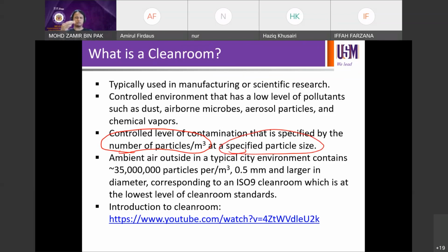So to put things into perspective, ambient air outside, if you go out to, say, Sungai Dua or Bayan Lepas, depending on the area of course, in a typical city environment like Georgetown, typically contains about 35 million particles per cubic meter. Yeah, 35 million particles per cubic meter. 1 meter by 1 meter by 1 meter. One box. With size 0.5 micron and larger in diameter. If you go to Georgetown, perhaps this is the typical number of particles that you will find in 1 cubic meter. 35 million particles, with sizes 0.5 micron and larger, corresponding to ISO 9.